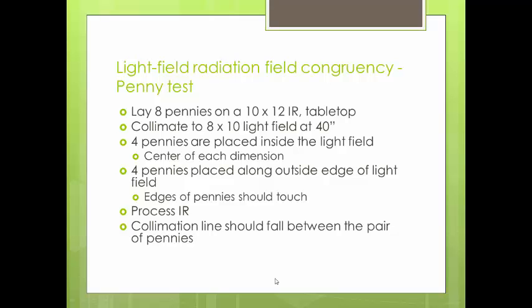This is extremely important to know because you don't want to be overexposing tissue. If your light field is smaller than your radiation field, you may be radiating tissue that unnecessarily needs to be radiated. Likewise, if your light field is larger than your radiation field, when you expose your image you may find that you have clipped anatomy — requiring a repeat image and still overexposing your patient.